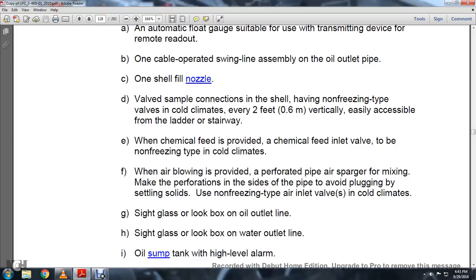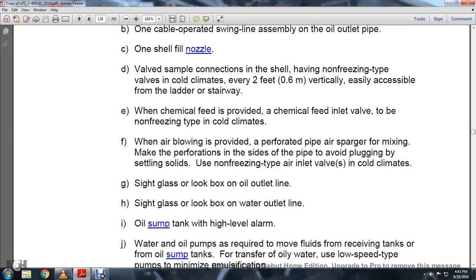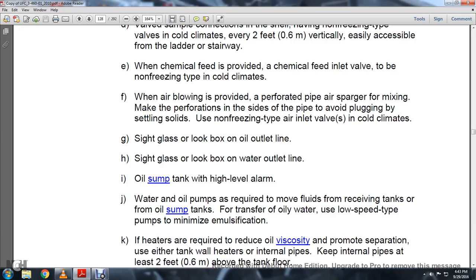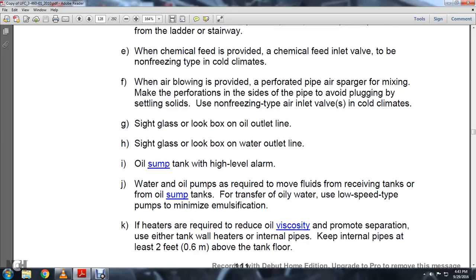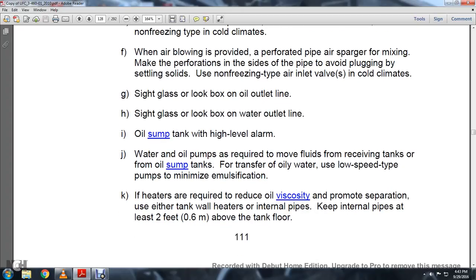When air blowing is provided, use a perforated pipe with air sparge for the mixing, with the perforations in the sides of the pipe to avoid plugging and settling solids. Use non-freezing type air inlet and valve in cold climates. Sight glasses: look-in box on the oil outlet line, and look-in box on the water outlet line. Oil sump tank with a high level alarm. Water and oil pumps are required to move the fluids in the receiving tank from the oil sump tanks for transfer of oily water; use low speed type pumps, minimizing emulsification.